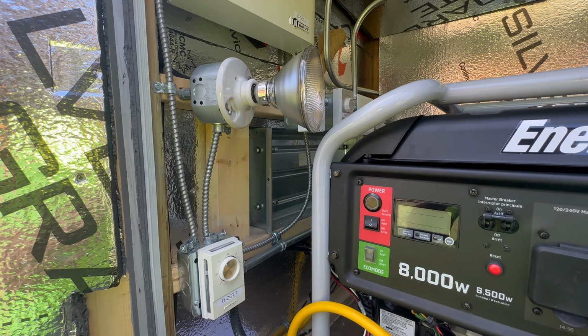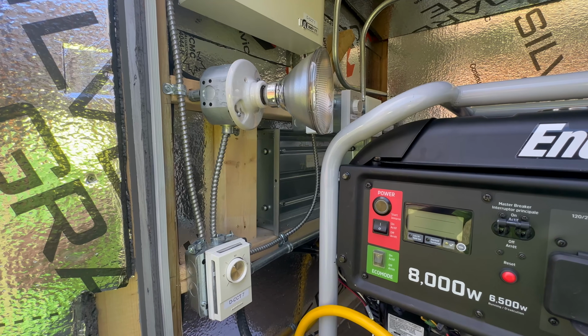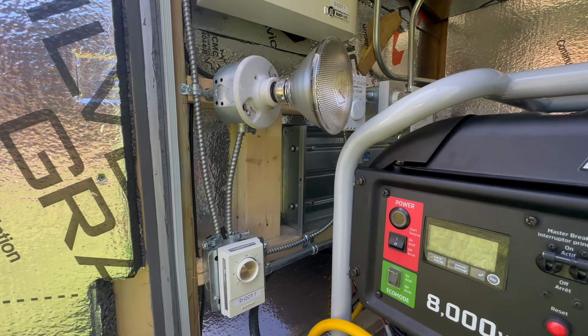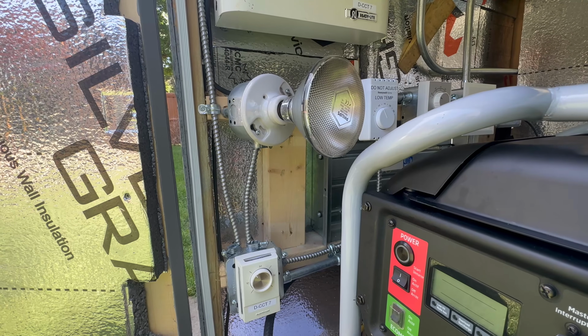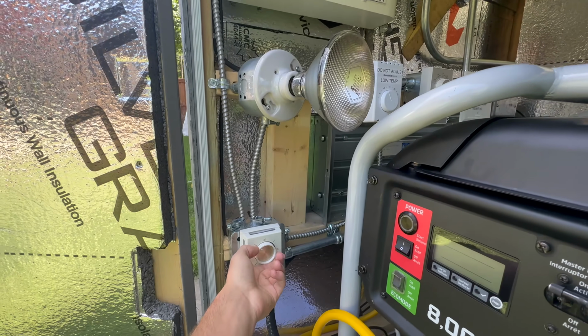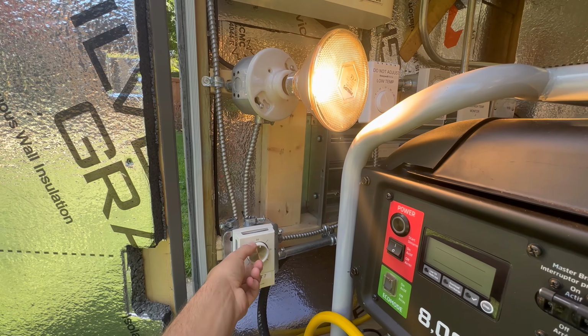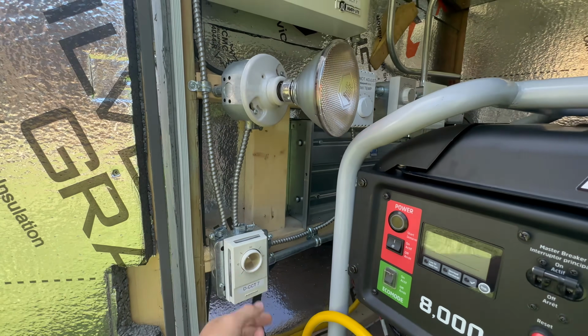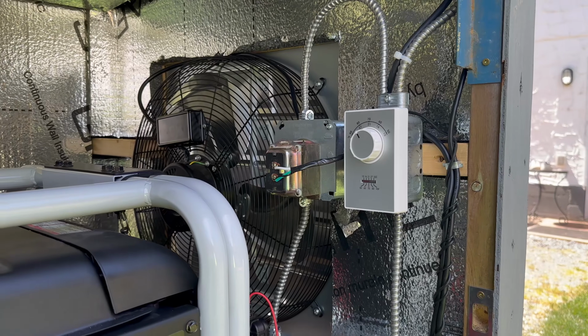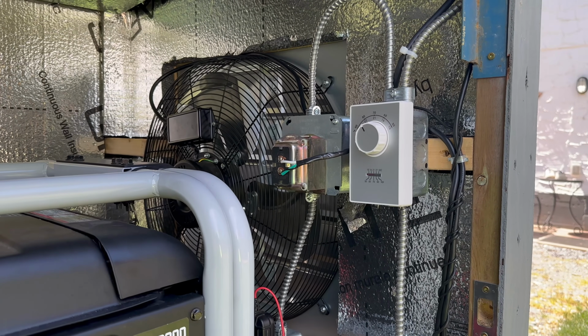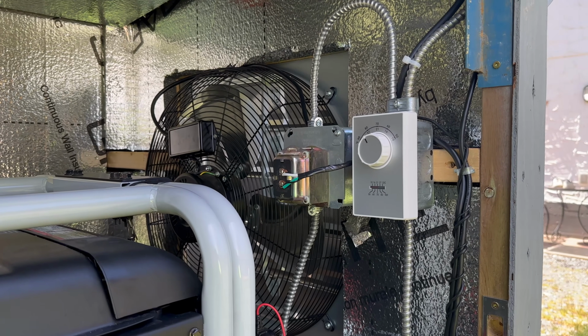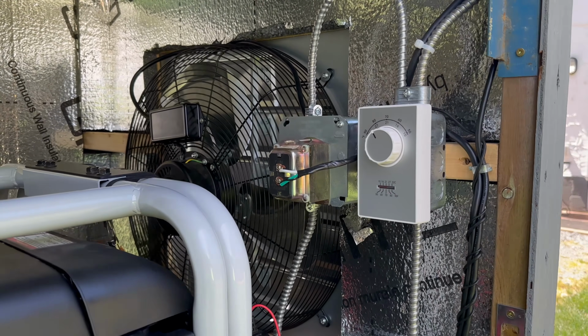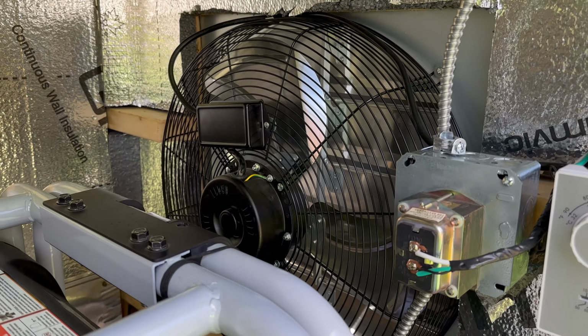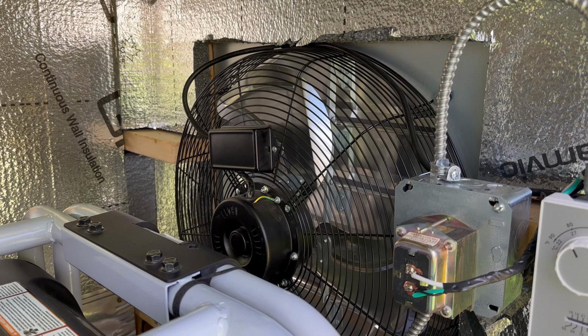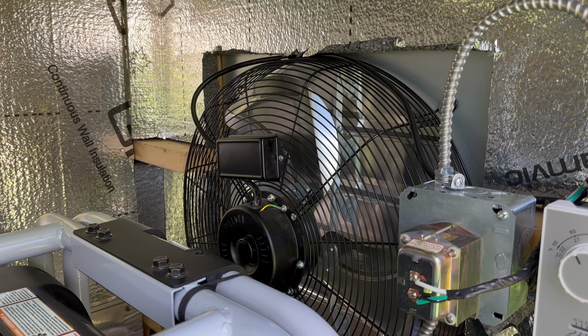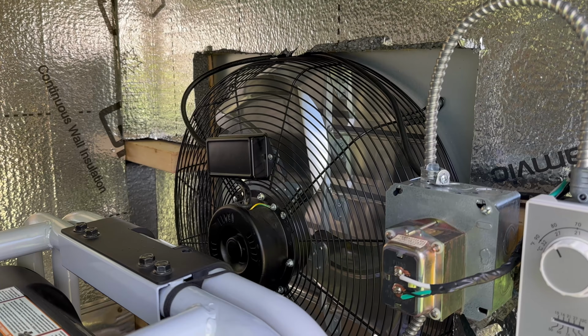In the generator building, to keep it at an optimal temperature for the generator start, I have a 250 watt incandescent light bulb on a thermostat, which will turn on at the desired temperature to keep the generator warm in the winter. And in the summertime and while the generator is running, I have a reverse acting cooling thermostat that is tied into this 24-inch fan to draw fresh air in to cool the generator building while it's running or on a hot day.